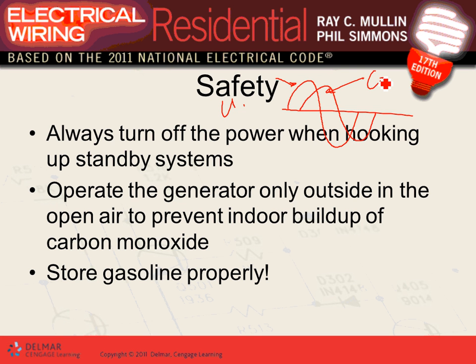So there are a lot of syncing issues when you put in your generator. The first and most important thing is that we'll talk about synchronizing generators, guys. And for dwellings, it's not an option. Almost for all dwellings, there is no synchronization whatsoever. So the most important thing when you bring in power is to disconnect the power. Here's my generator, here's my utility. I need to have a disconnect here that makes sure that it will either go to the generator or to the grid, but not both at the same time. Can I have a thumbs up, chat? We understand. So it's important for a dwelling that when you put your generator on, your utility is off, and vice versa. You can't put them on at the same time.